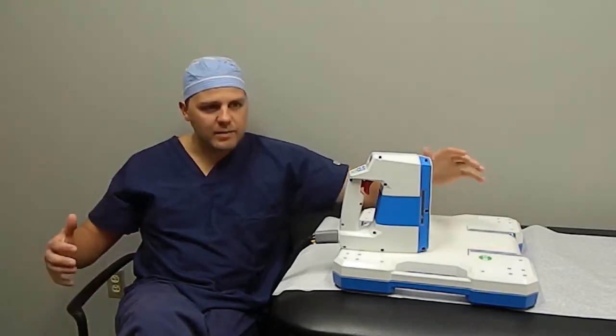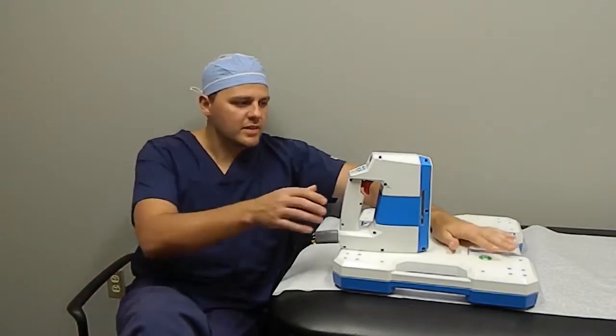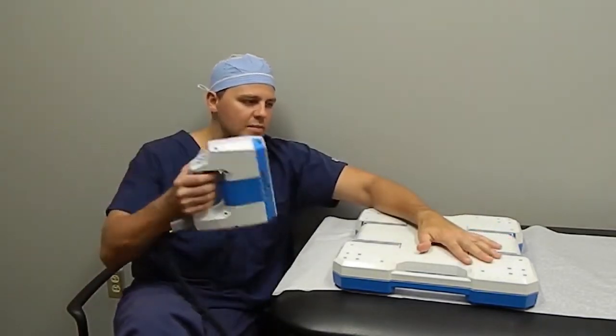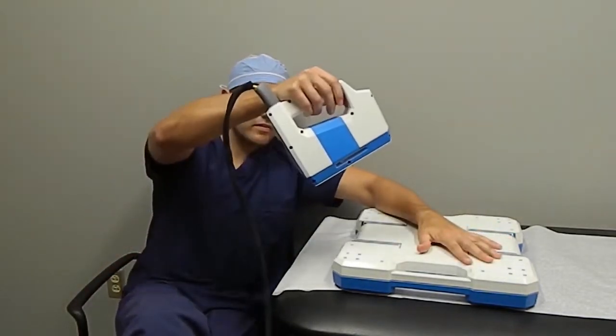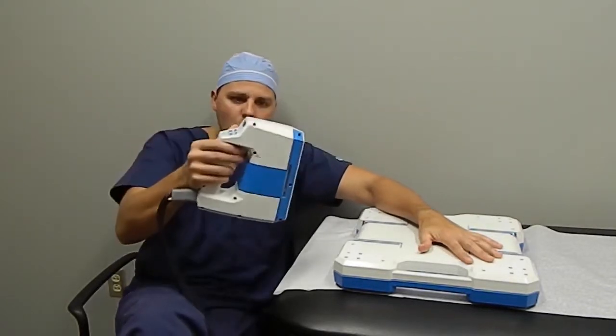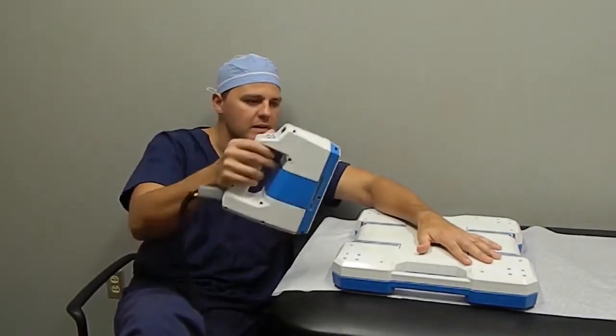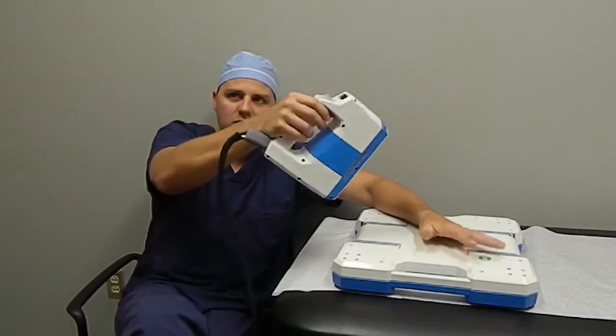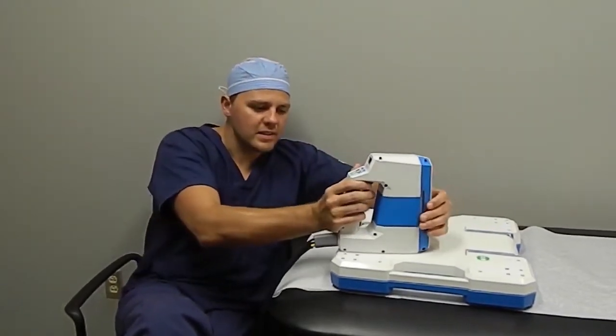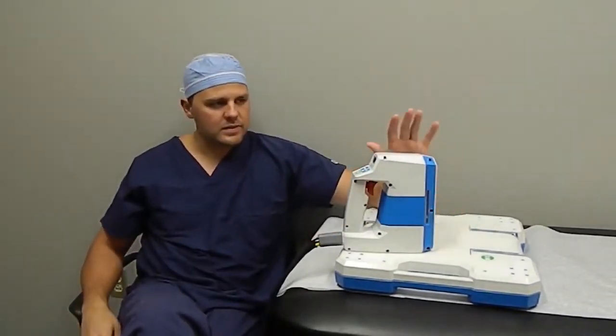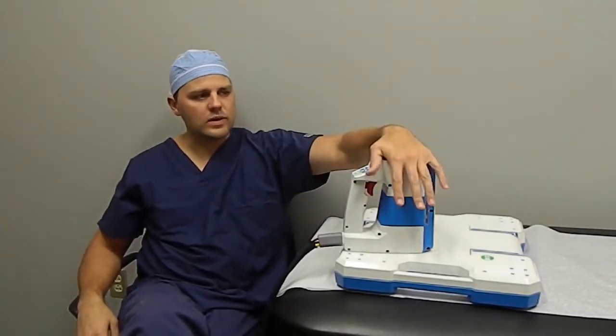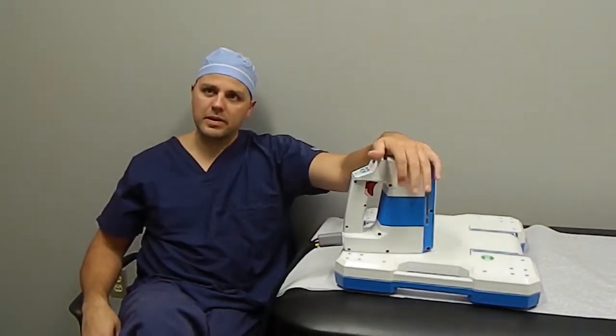Sometimes the hand moves or shakes when you're trying to get the image. Here you've got absolute stability because you don't have to move the hand. We've got a quick flash of 50 milliseconds, which is about 1/10 the time of the competitor, so there's less chance for motion artifact or distortion. We've sort of taken all that into consideration. This was not created with one voice. This was created with many voices, many parts of feedback.